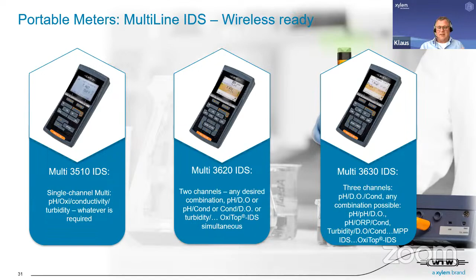If this is interesting, then of course we have the multi 3620 or multi 3630, which are able to measure simultaneously with 2 parameters in any combination, or 3 parameters in any combination. So that means you can put in 2 pH or 2 DO or 2 conductivity or conductivity and DO. And so any combination is possible. Also turbidity, of course. So everything that's desired is possible for this measurement.